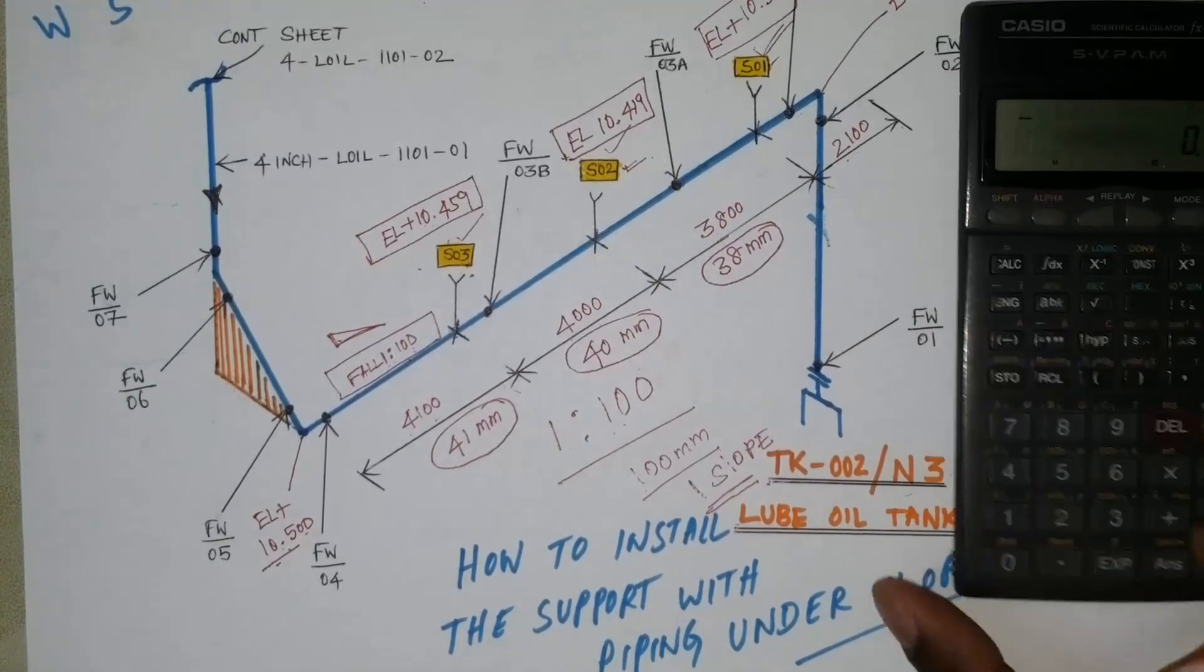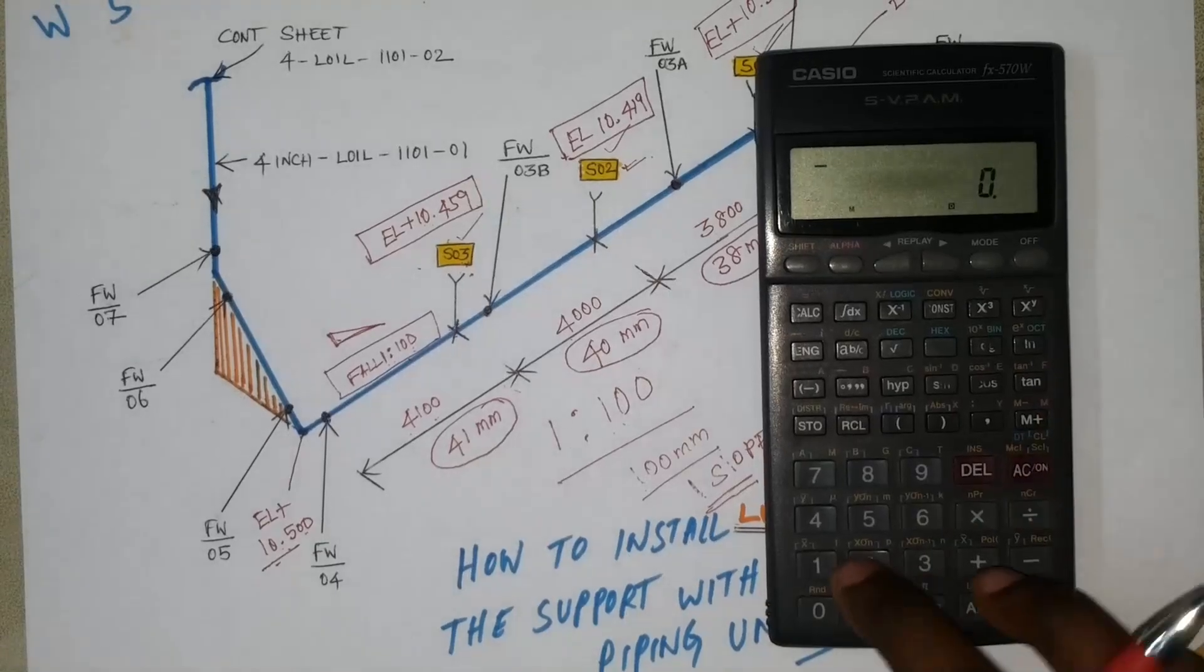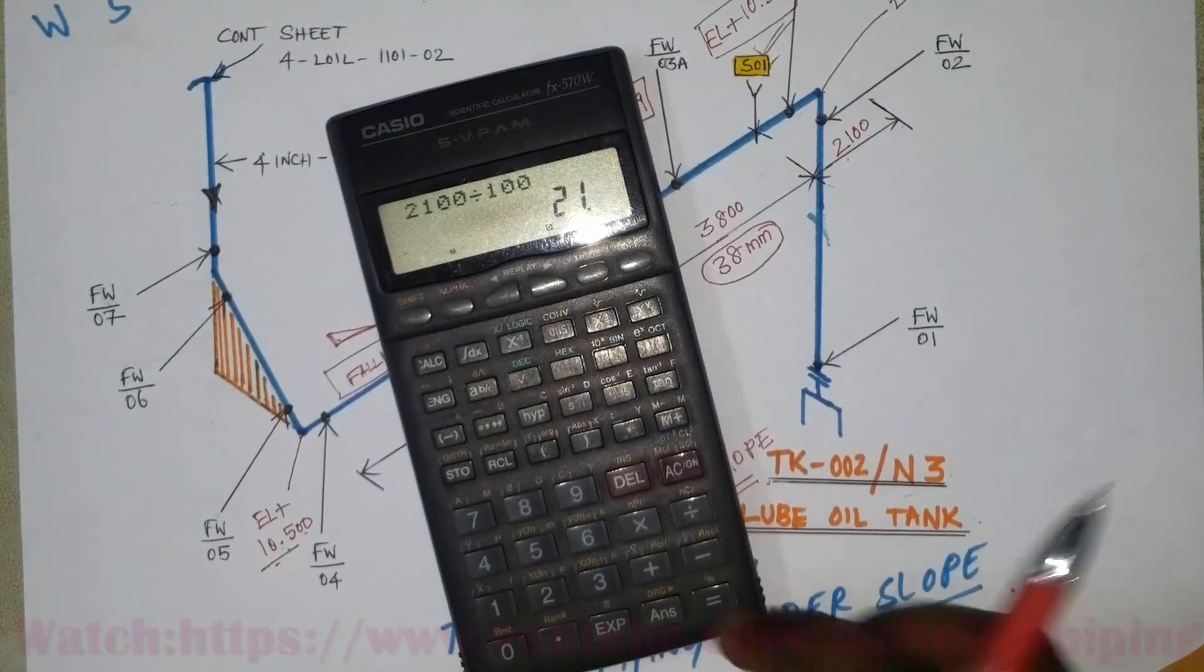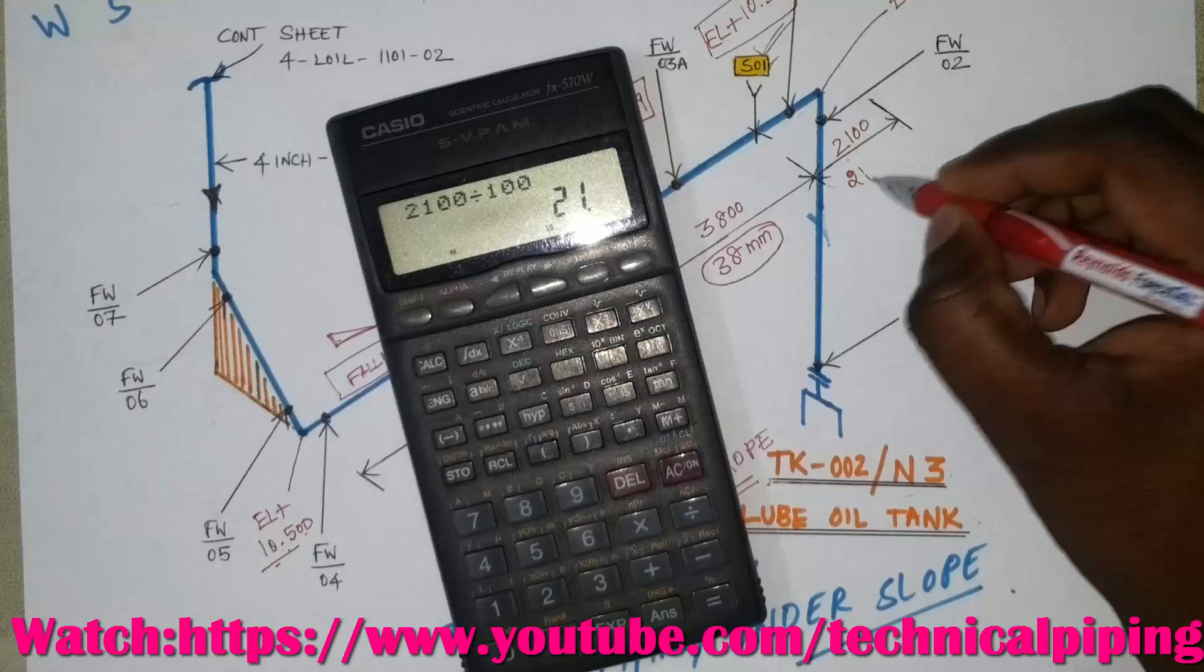So 2 meter 100 divided by 100 is 21 mm. We have to decrease the elevation from support number 1 to this elbow.